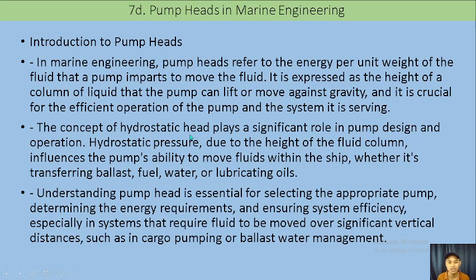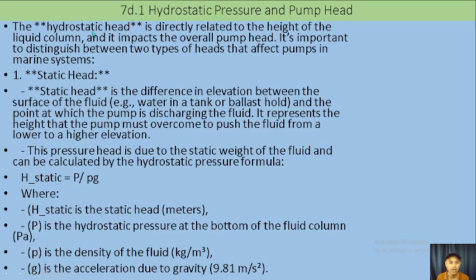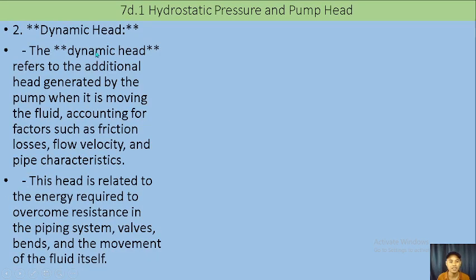The concept of hydrostatic head plays a significant role in pump design and operation. So let's continue. We have different types of hydrostatic head. First, we have the static head. Static head is the difference in elevation between the surface of the fluid and the point at which the pump is discharging the fluid. It represents the height the pump must overcome to push the fluid from a lower to a higher elevation.